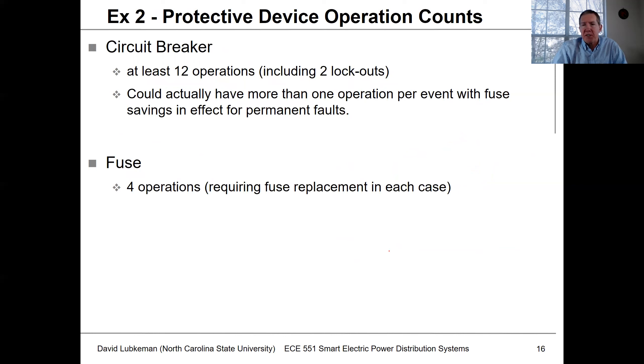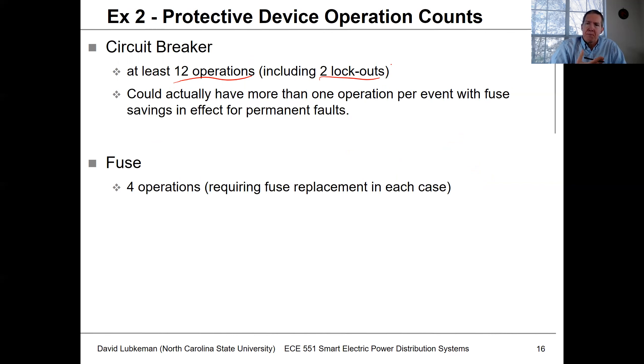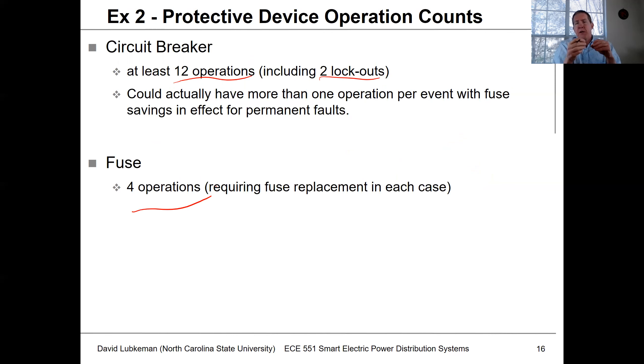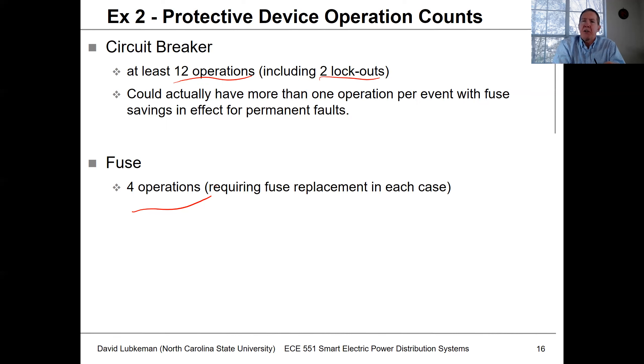Looking at protection device operation counts from the table, the circuit breaker will operate at least 12 times — including two lockouts — and may operate more because clearing temporary events requires two or three shots. The fuse will operate four times, requiring a crew to replace it each time. As Mr. Guida noted, there's a replaceable fuse link in the cutouts: the crew uses a hot stick to remove the blown fuse link, replaces it, and pushes it back into the cutout.